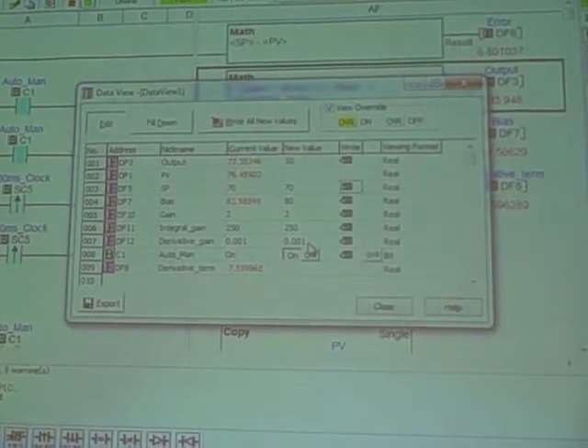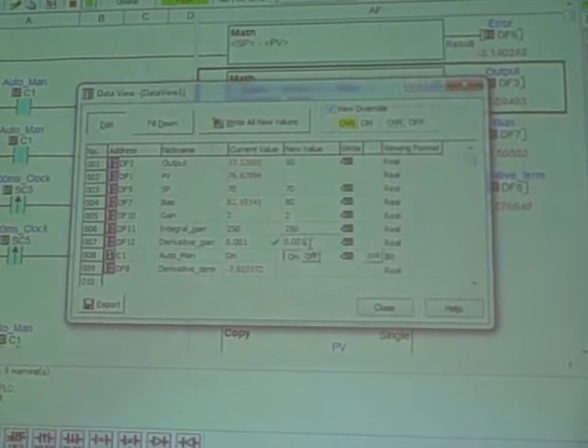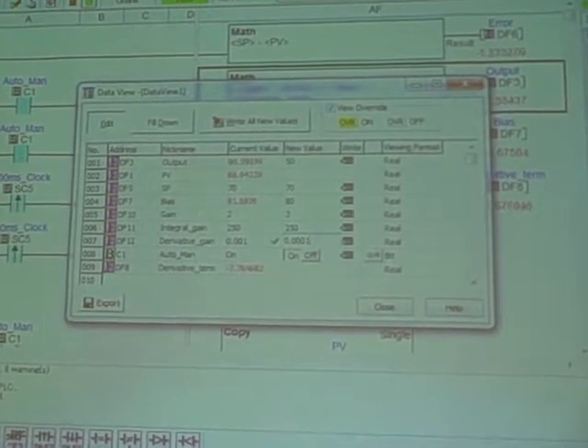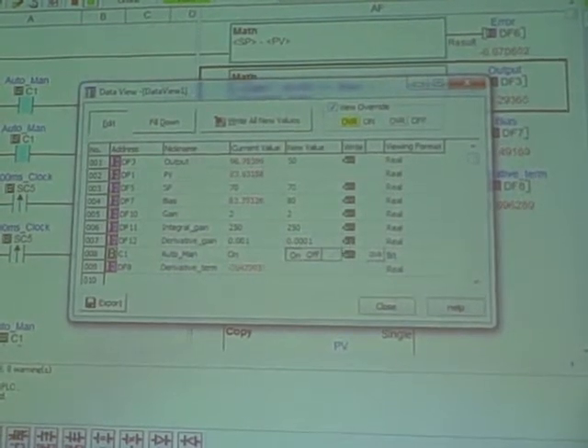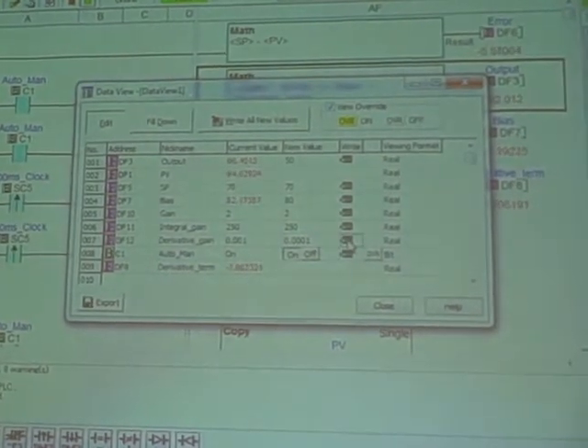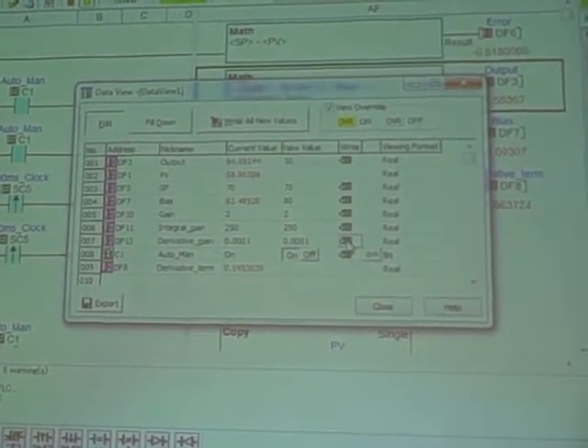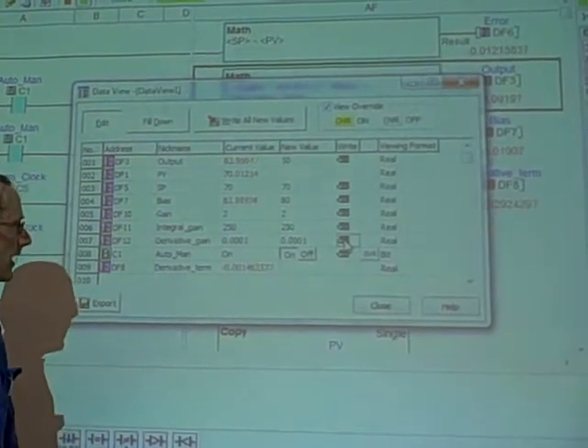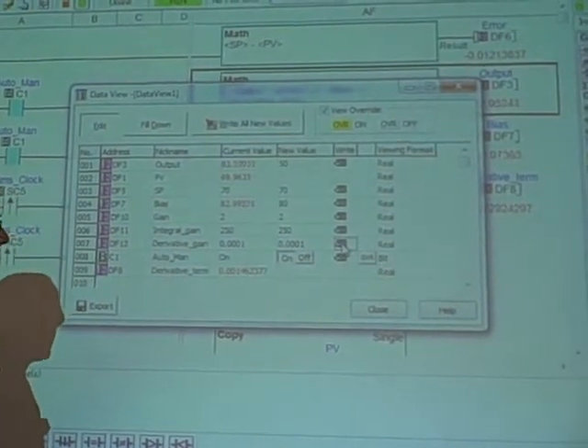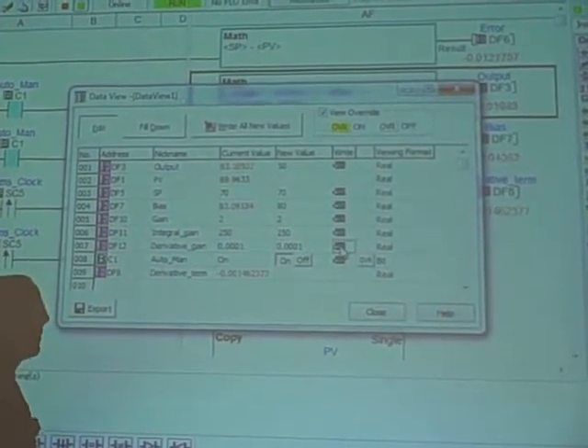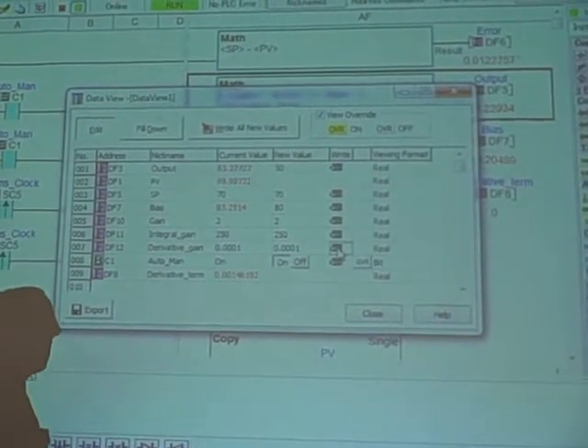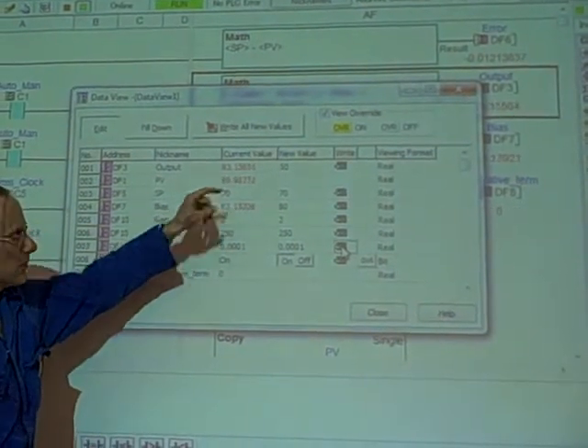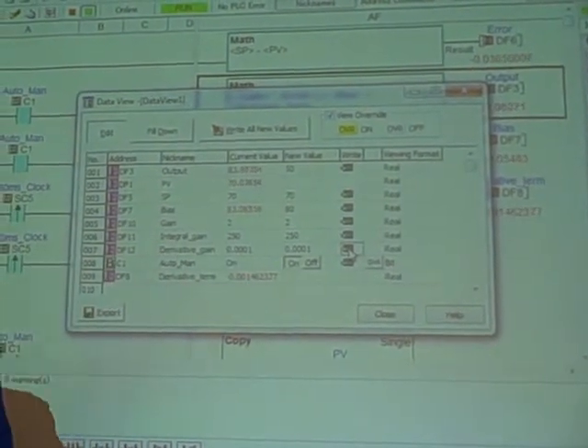Again, remember this is minutes, not seconds. So I go there, enter one more zero, enter that, and it stays 0.0001. What we have here is a very fast acting responsive PID control system. Setpoint is 70%, PV of 70%.